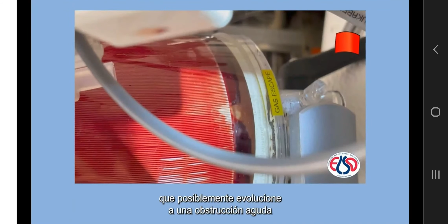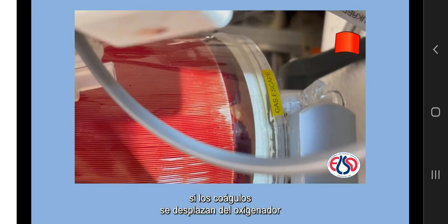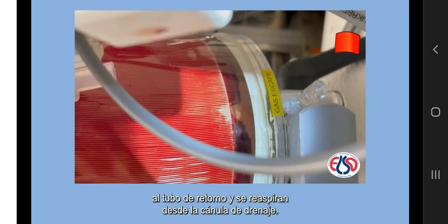Maybe you have a visible major clot, possibly evolving to an acute blood flow obstruction, or a clot in a dangerous location, meaning on the arterial side of the oxygenator, proximal to the membrane lung outlet, with risk of acute return cannula thrombosis, systemic embolism on VA ECMO, or pulmonary embolism on VV. Also consider that you could have acute drainage insufficiency if the clots move from the oxygenator to the return tubing and are re-aspirated from the drainage cannula.